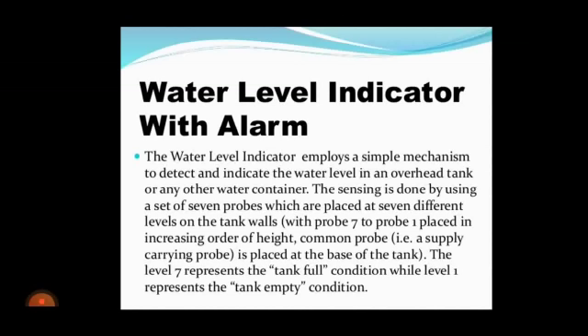The sensing is done by using a set of 7 probes which are placed at 7 different levels on the tank walls. With probe 7 to probe 1 placed in increasing order of height, a common supply-carrying probe is placed at the base of the tank. Level 7 represents the tank full condition while level 1 represents the tank empty condition.